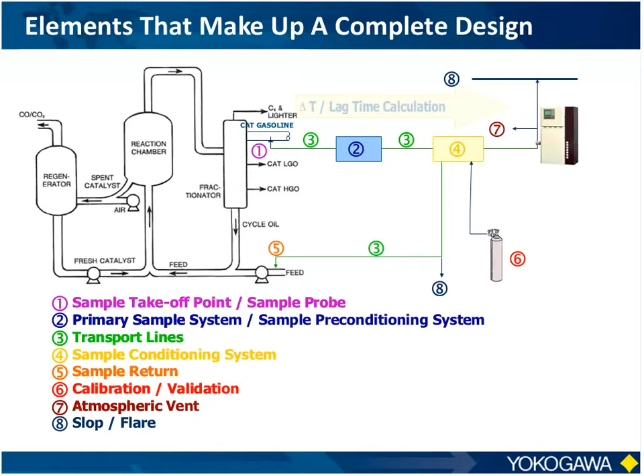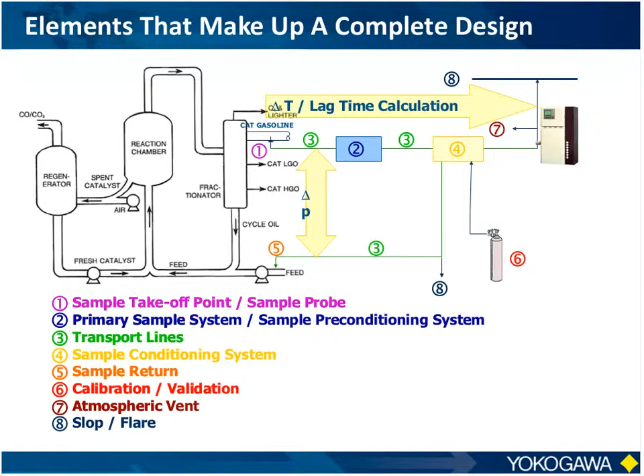I need to return the sample. Again, I just can't dump it down the drain or dump it in the air, at least not this day and age, not like the old days. I need to have a mechanism to introduce calibration and validation gases. And then if the analyzers themselves have any vent gases or slop, that needs to be accommodated and captured and returned. So all of these elements need to be thought of and considered, including lag time. Again, the analyzer might be mounted 100 or 200 feet away from where the sample is taken, because that was the closest place for the shelter. And I need to make sure I can transport that sample without a huge delay.